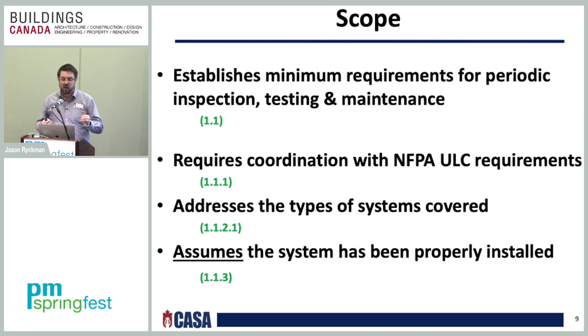We obviously care about the design and installation part of your system, but the whole basis of this inspection, testing, and maintenance document is to make sure that your system is operational, period. Now, that doesn't mean that if an inspector finds any design or installation deficiencies, they can't record that to the owner. They can, but it would be as a separate document, not on the inspection form. So it's basically an informational document, telling the owner or owner's representative that you do have design and installation deficiencies that you need to take care of.